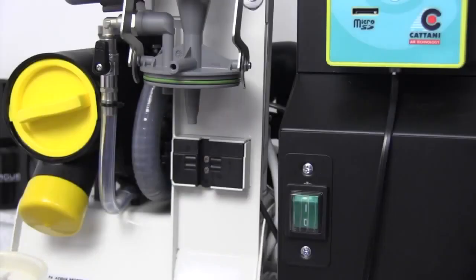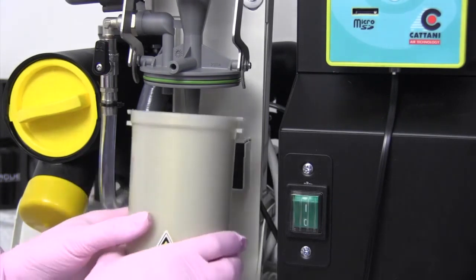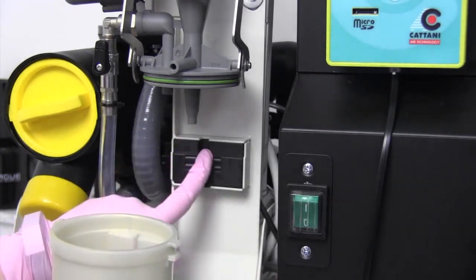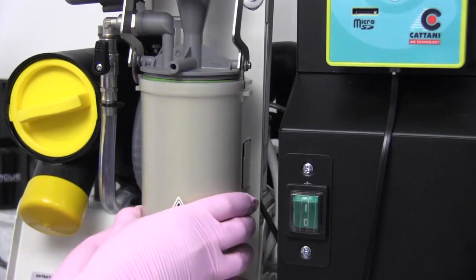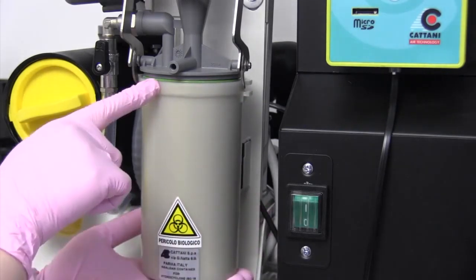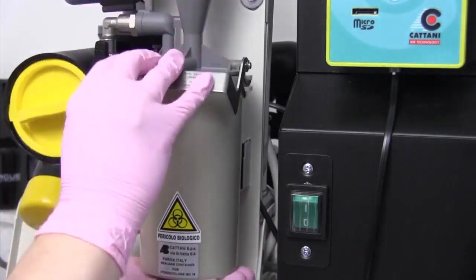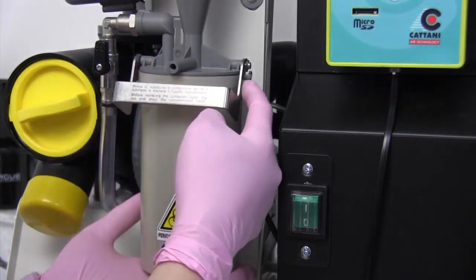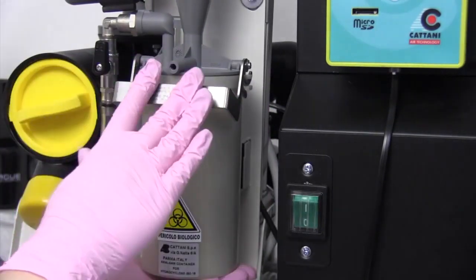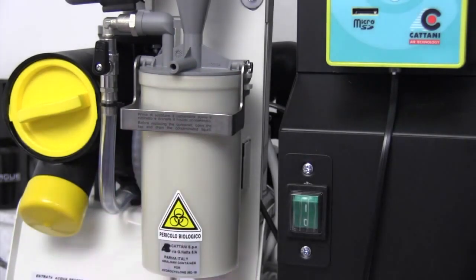Number 7, locate the recess of the pot into the amalgam sensor. Then lift the pot so it just touches the O-ring and then push the handle down. The handle will locate the lugs on the side of the pot and bring it up into the correct position. If there is any resistance, then the pot isn't located in the correct position.